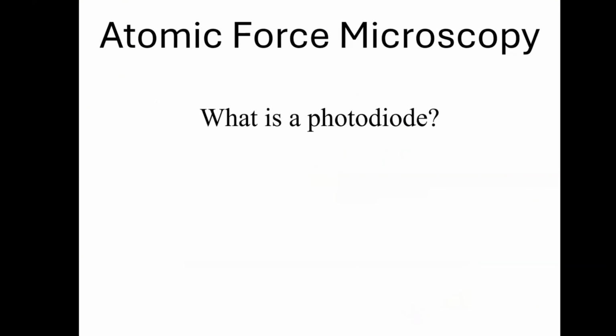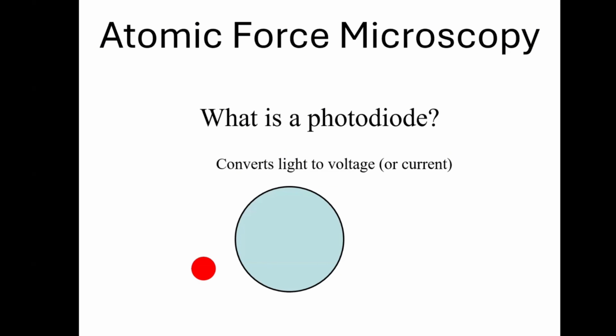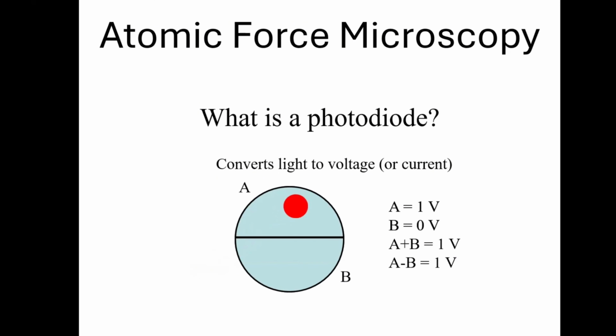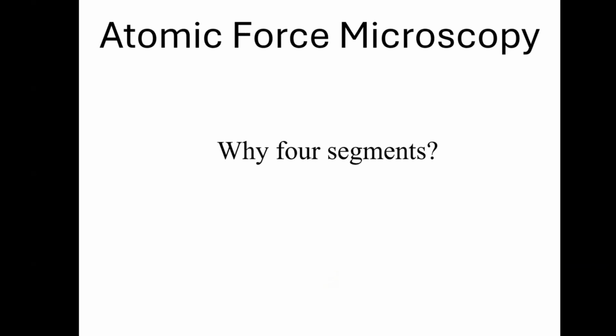But what is a photodiode? A photodiode converts light to voltage. So as we move the laser onto the photodiode, we start to see some signal. We can split the diode, and we can see that we get 1 volt from the top half and 1 volt total. We can zero the difference between the top and the bottom by placing the laser in the center. And if we have 4 quadrants, we can center the spot left to right as well. This is something you do, or the AFM does automatically at the start of every experiment. Why 4 segments? Well, AFM can be used to measure friction and torsional forces as well.